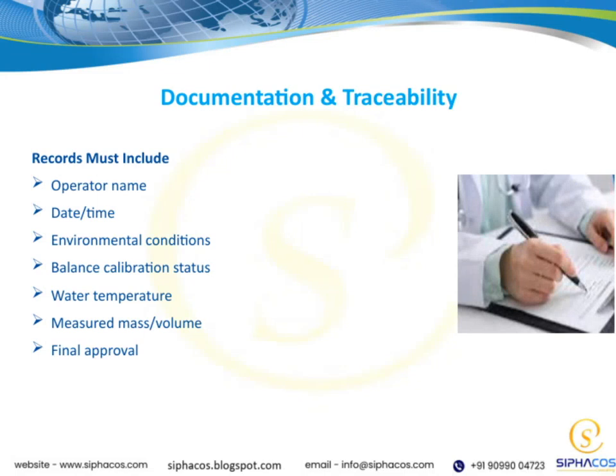Let's talk about documentation and traceability, which are crucial for maintaining quality and accountability. When recording our data, we need to include several key pieces of information. First, the operator's name, so we know who performed the task. Next, the date and time. This helps us track when each step was completed. Environmental conditions are also important, as they can impact the measurements. We should record the status of the balance calibration to ensure our equipment is accurate. Water temperature is another vital factor, especially if it influences the results. The measured mass or volume must be carefully documented to maintain data integrity. Finally, the final approval signifies that the record has been reviewed and authorized.